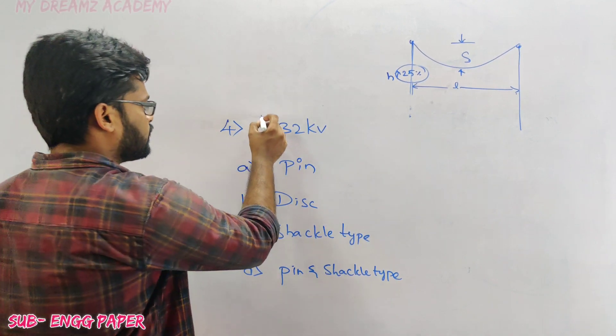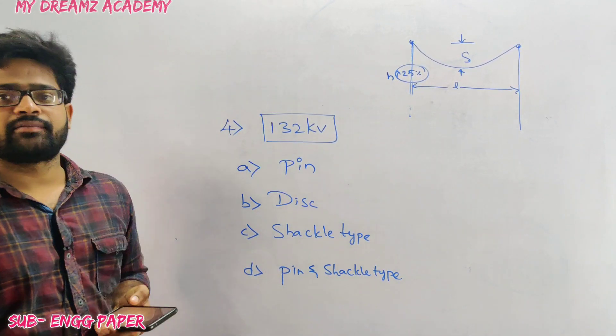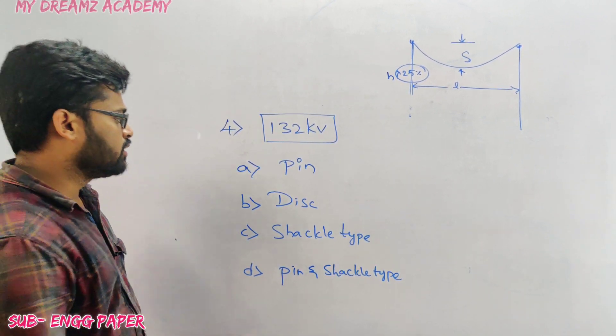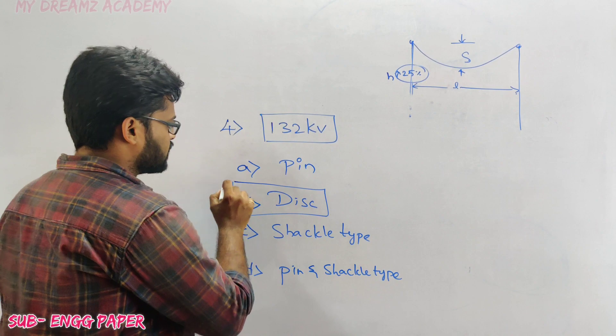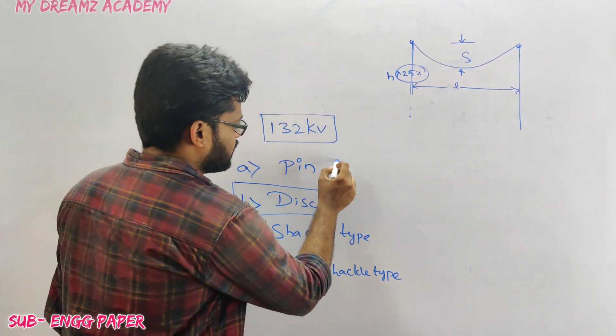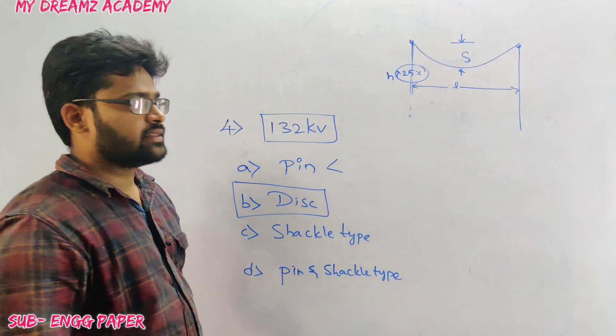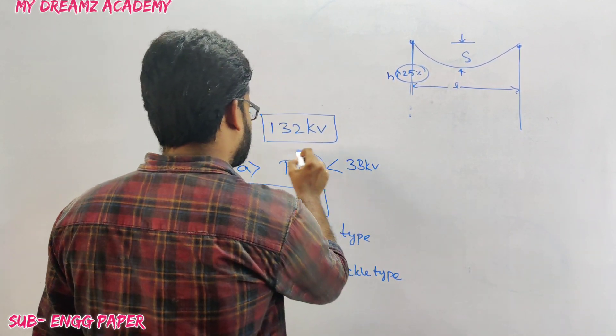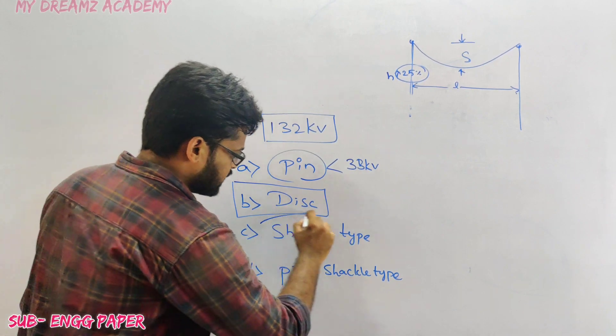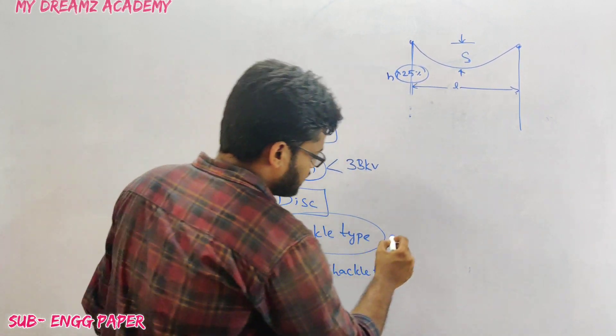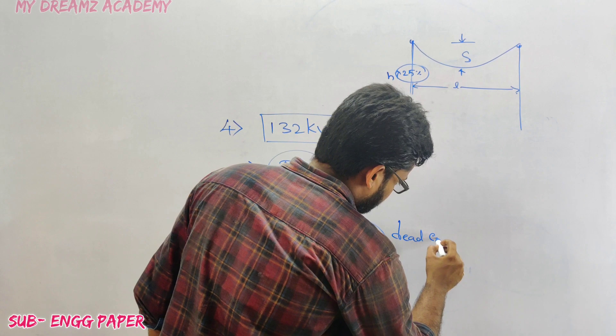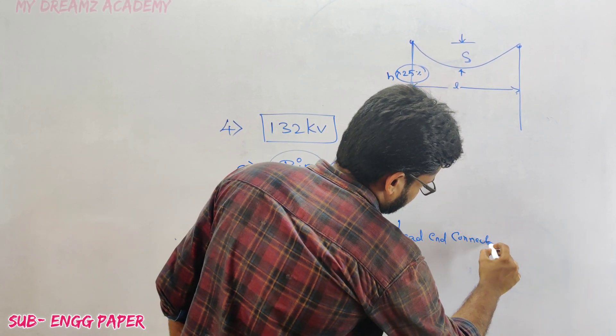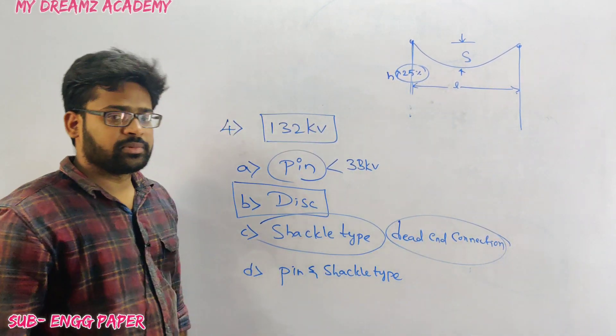If the rating is 132 kV, we use disk type insulators. If the rating is less than 33 kV, we use pin type insulators. Shackle type insulators are used at dead-end connections.